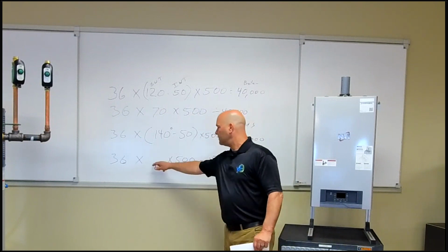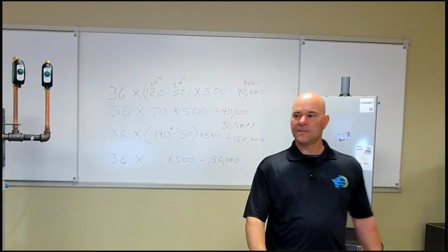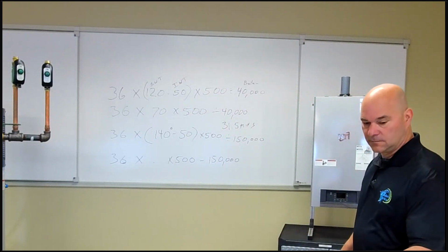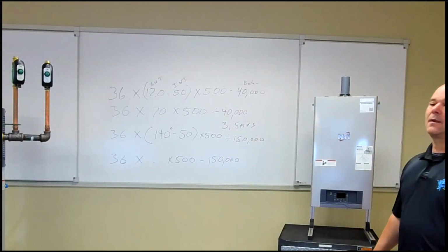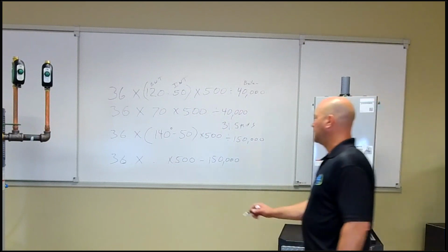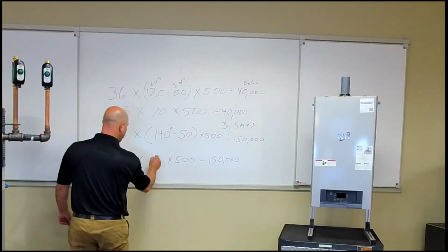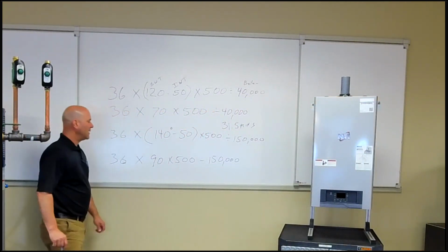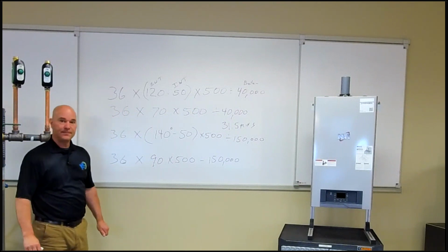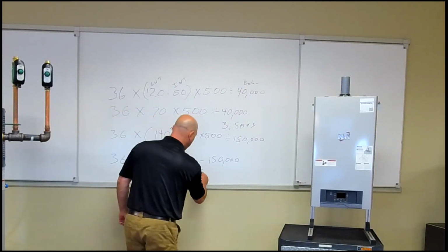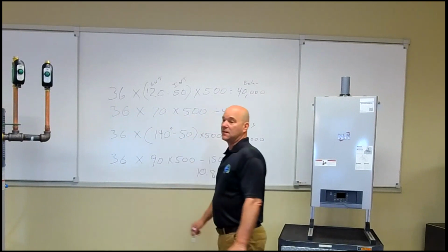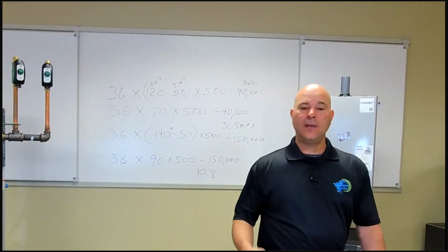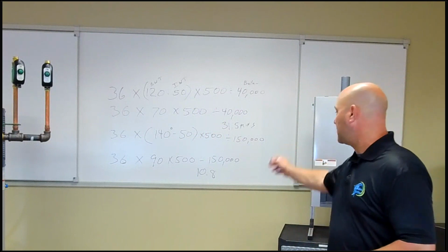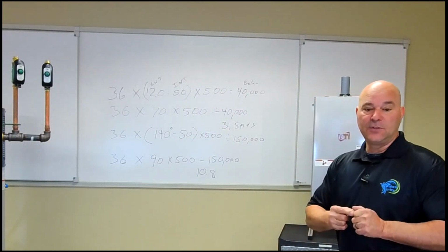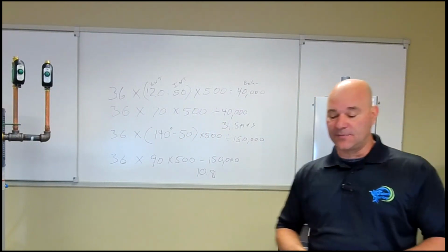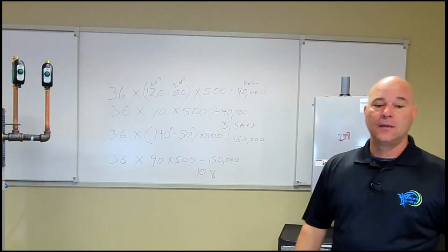What's my number here? Oh, they're getting it. What is it? Well, I mean, they finished the whole. They did. All right. So they know that this is 90. Yeah. How long did it take to make hot water, Jim? 10.8 minutes. That's pretty standard. If you pipe and plumb and you have a boiler that can drive an indirect to full capacity, you'll make hot water in usually less than 15 minutes, 12 minutes, let's call it.